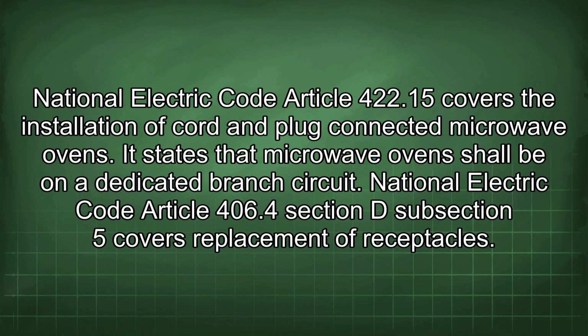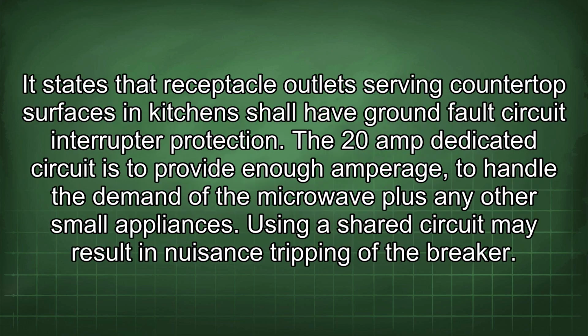National Electrical Code Article 422.15 covers the installation of cord and plug connected microwave ovens. It states that microwave ovens shall be on a dedicated branch circuit. National Electrical Code Article 406.4 Section D subsection 5 covers replacement of receptacles. It states that receptacle outlets serving countertop surfaces in kitchens shall have ground fault circuit interrupter protection. The 20-amp dedicated circuit is to provide enough amperage to handle the demand of the microwave plus any other small appliances. Using a shared circuit may result in nuisance tripping of the breaker.